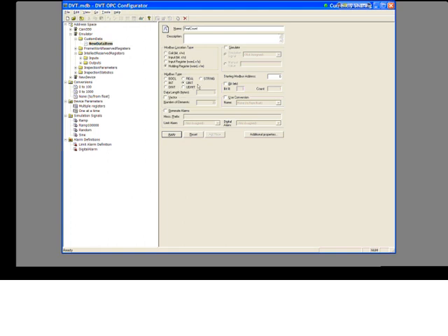The type of data does need to change, and you have to choose the type according to what you configure in Intellect. And this is where you have to do a mapping between the Intellect data types and the OPC server data type. Short, we said it was a 2-byte int. So that's called int in this case. We can see that it is a 2-byte value here. We have to specify the starting Modbus address. Remember, that was 16 in our case, and that's pretty much it.